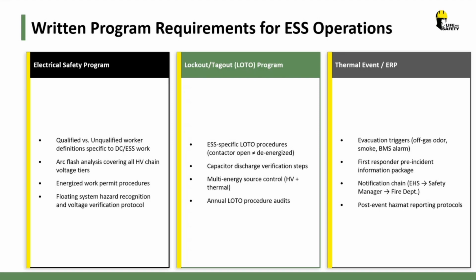This applies to maintenance activities. Guess what, it also applies to manufacturing batteries. When you're making ESS systems, you're doing live work, an energized work permit. Now, if it's part of what you're manufacturing, this permit is essentially your SOP—the document on how you construct a battery pack is your energized work permit. But in the maintenance activity world, this would be for situations where you're not going to shut it down.